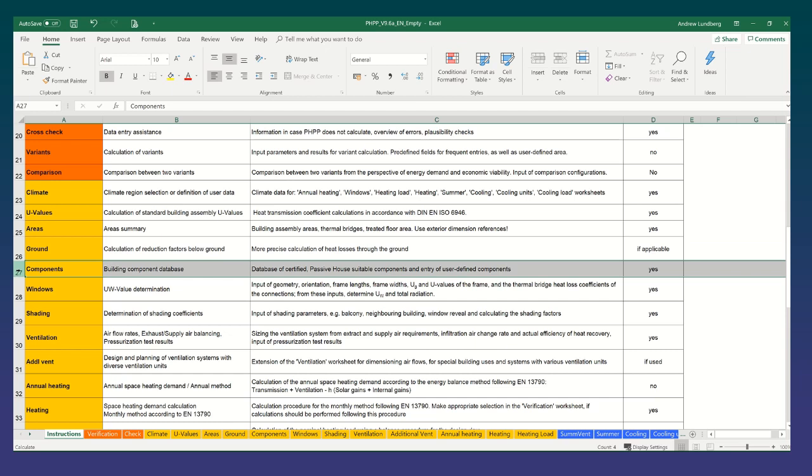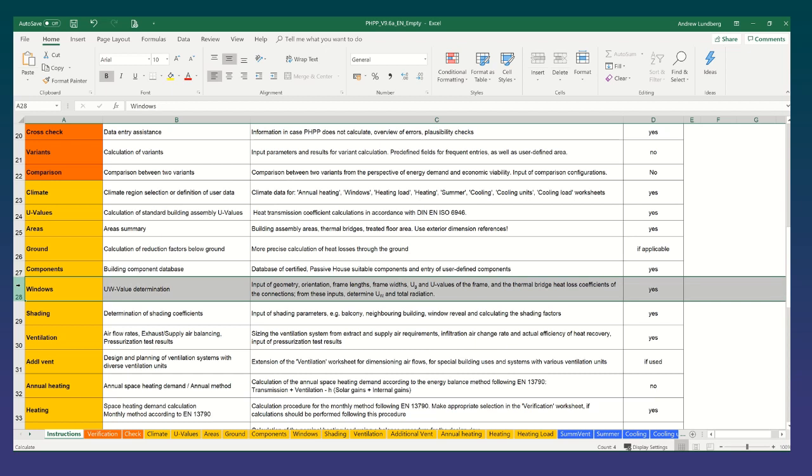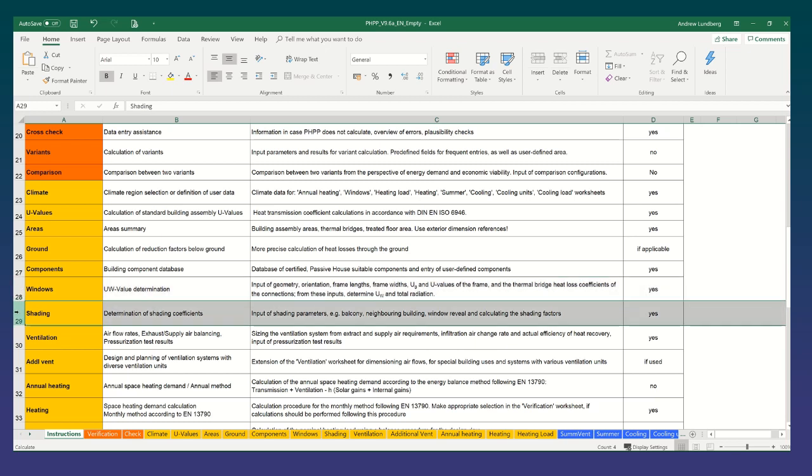Next thing you would look at are the components. So this is where you then enter in data for your windows and for your ventilation system and if applicable maybe your elements of your heating system although they've separated that out a little bit now in the latest version to the PHPP. The windows tab is very important. This is where you'd input the geometry, orientation, frame lengths and frame widths. Ug and Uf values of your frame would be selected. Although they're entered in the separate in the components tab just before that but selected then from drop down menus for input in that sheet and then thermal bridge heat loss coefficient of the connections and from those inputs the overall U value for the window is determined. So that will determine the heat losses through the window and the total radiation is also calculated to calculate your solar gains based on the g-value of the glazing and the orientation and area of the window as well as any shading.